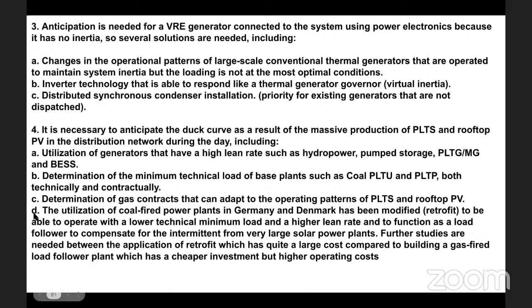D, the utilization of coal-fired power plants, as in Germany and Denmark, has been modified (retrofit) to be able to operate with a lower technical minimum load and a higher ramp rate and to function as a load follower to compensate for the intermittency from very large solar power plants. Further studies are needed between the application of retrofit, which has quite a large cost, compared to building gas-fired load follower plants, which has a cheaper investment but higher operating cost.